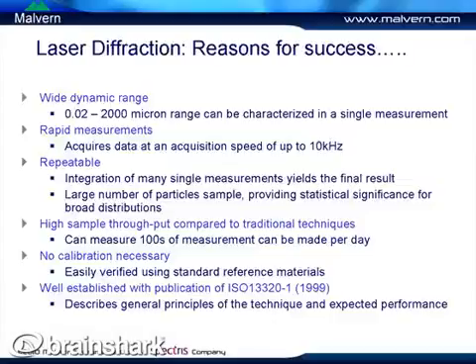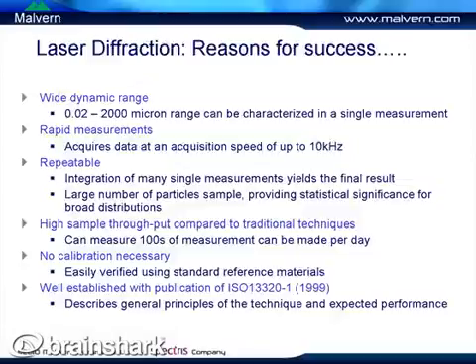The measurements themselves are quite fast, so we can make hundreds of measurements in a day, and that's a lot quicker than traditional techniques such as sieving. The instruments themselves are not calibrated as such, because laser diffraction is a first principles technique — there is no dial on the instrument that we can turn to make it give us the right answer. So instead, we verify the instrument using a standard reference material, such as a latex or glass bead sample, to make sure the instrument is operating correctly.